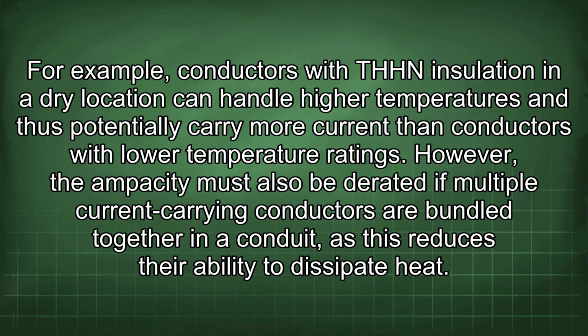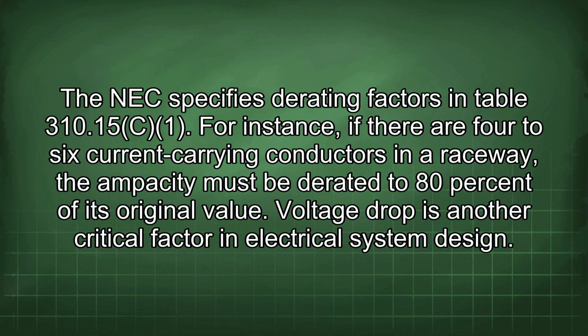However, the ampacity must also be derated if multiple current-carrying conductors are bundled together in a conduit, as this reduces their ability to dissipate heat. The NEC specifies derating factors in Table 310.15. For instance, if there are 4 to 6 current-carrying conductors in a raceway, the ampacity must be derated to 80% of its original value. Voltage drop is another critical factor in electrical system design.